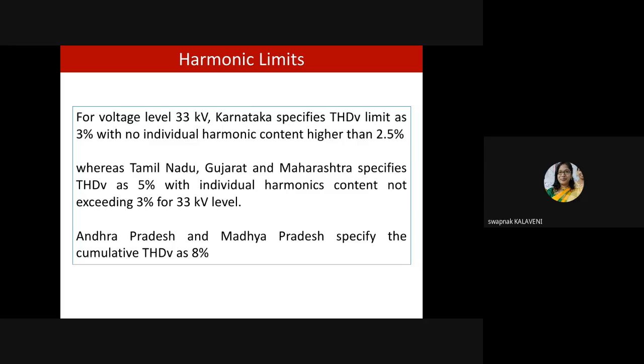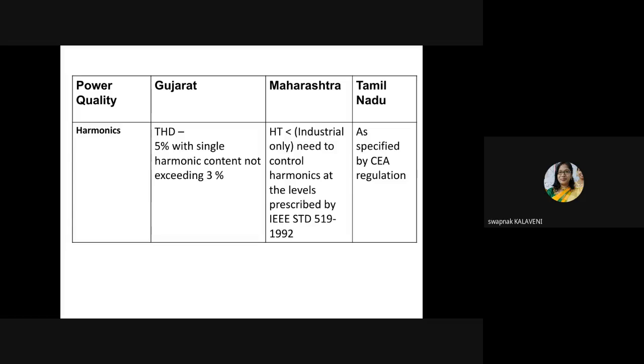If you think about voltage at the 33 kV level, again the THD level is further reduced to 3%. What impact does it have? If you are reducing this percentage level further, it means we are improving the quality of the system. In Tamil Nadu, it is THD 5%, individual harmonic 3%. In Andhra Pradesh and Madhya Pradesh, about 8% is permitted. You can see Gujarat is 5% THD, single harmonic 3%.